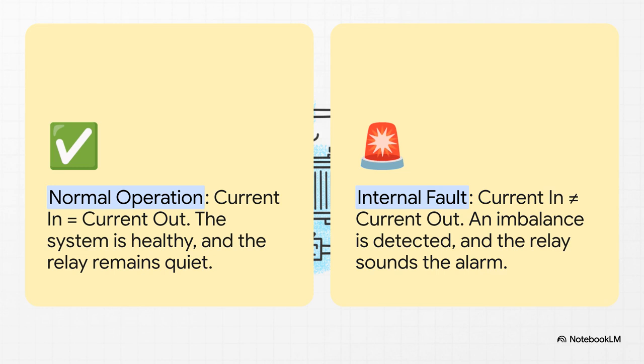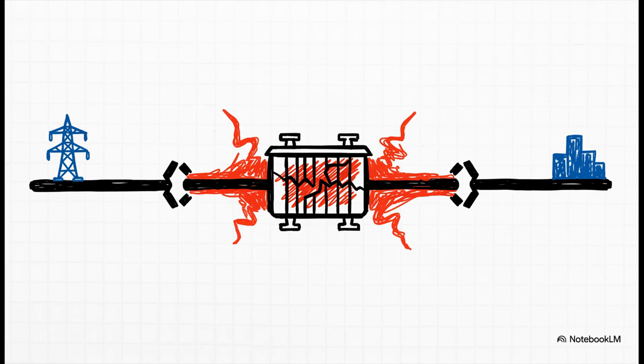In a healthy transformer, whatever current goes in has to come out. It's a perfect one-to-one balance. The protective relay sees this perfect balance, and it just chills, it stays quiet. But if something goes wrong inside the transformer, some of that current gets lost. Suddenly, what goes in does not equal what comes out. The relay sees this imbalance and immediately sounds the alarm. That imbalance is a critical symptom. It's the grid's equivalent of an internal bleed. It tells the whole system that this specific organ is in trouble. That alarm signal instantly trips the circuit breakers all around it, isolating the damaged transformer before it can harm anything else.